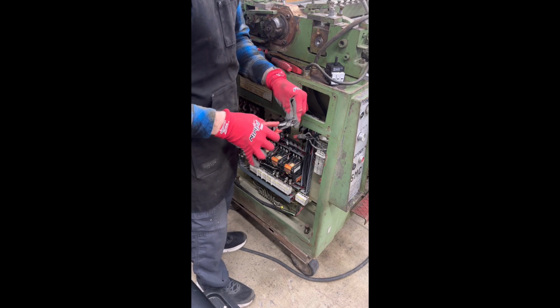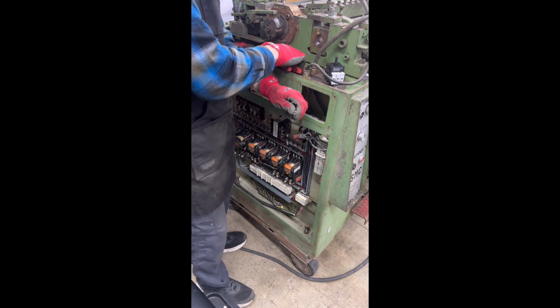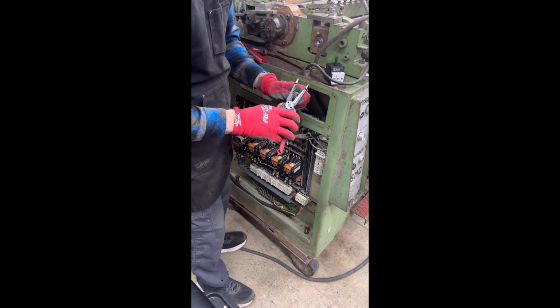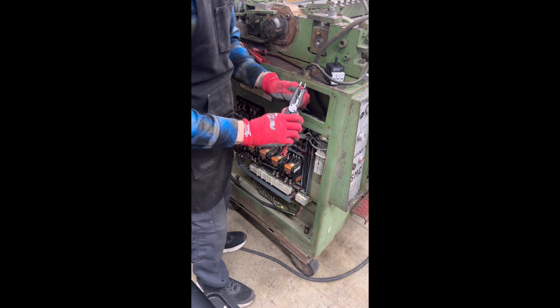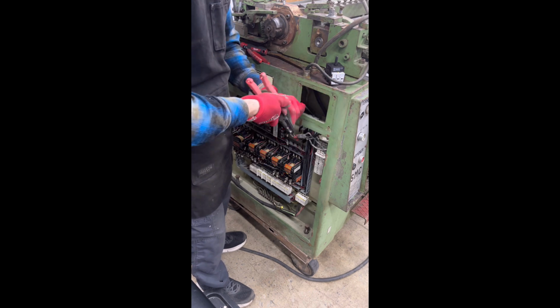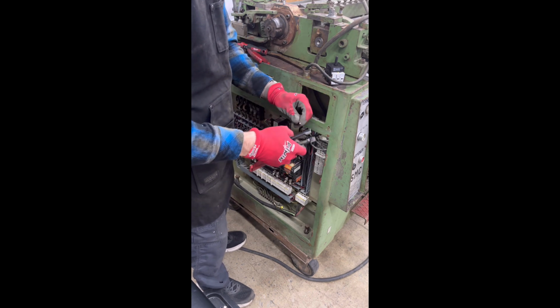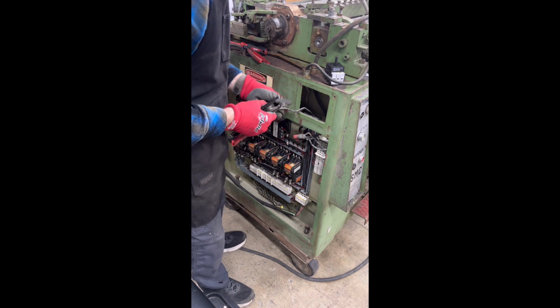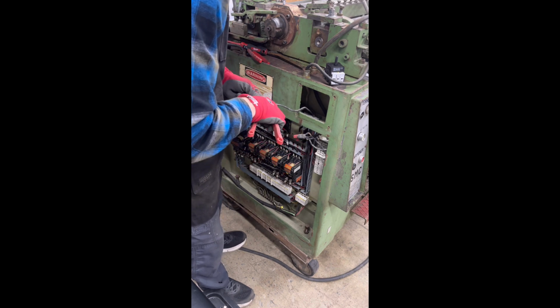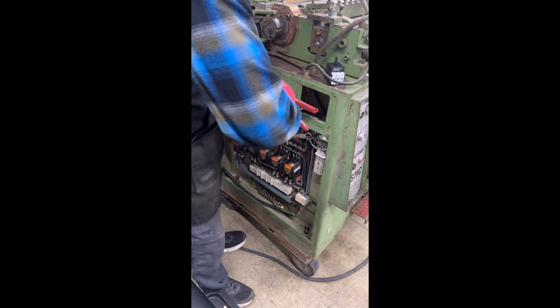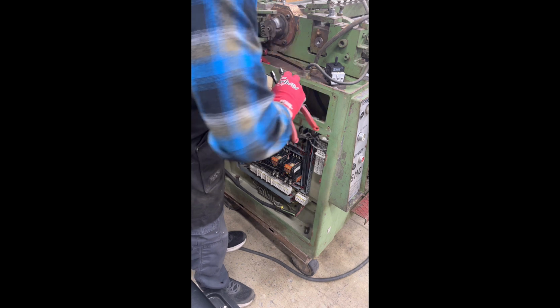These main wires that went to the factory isolation switch — here I'm trimming them back. They were pretty beat up from being inside the wire nut and fairly corroded. So I always like to, if there's enough wire, trim off the end and strip back some new copper to get a good contact.